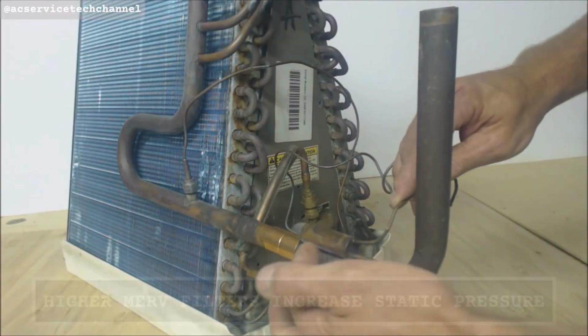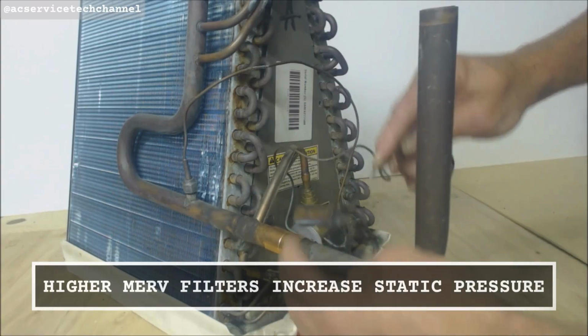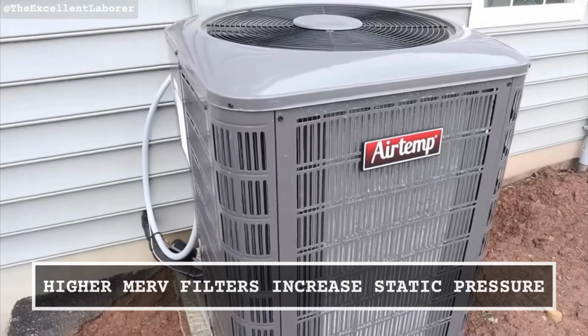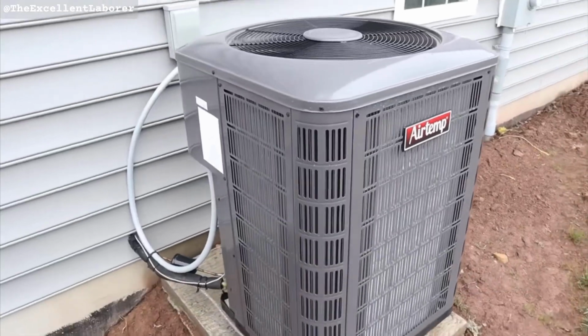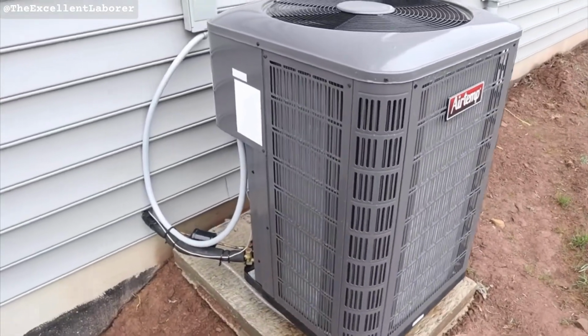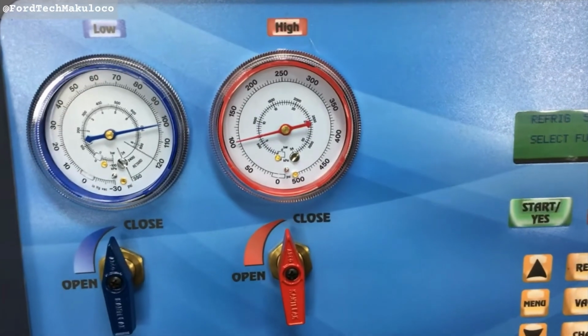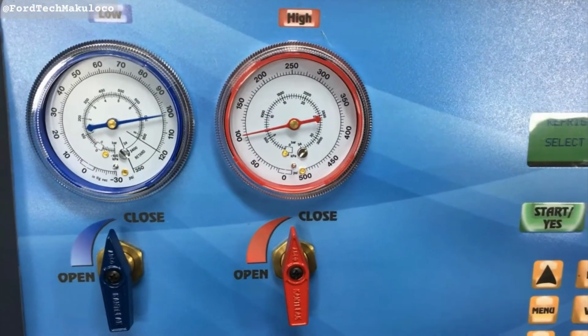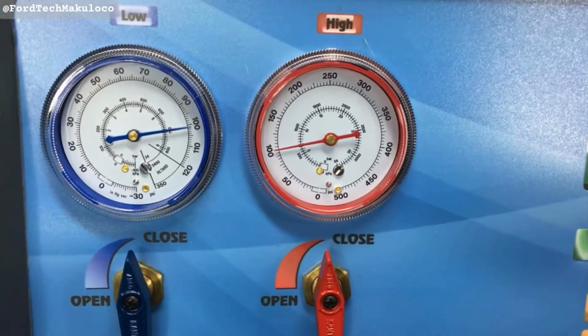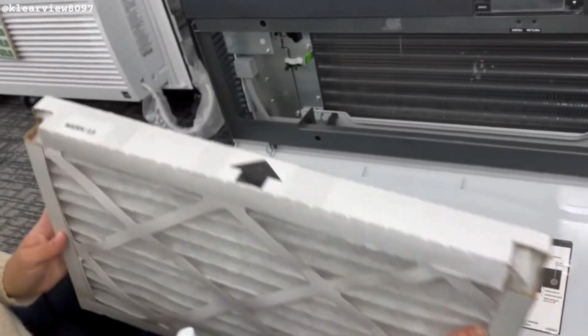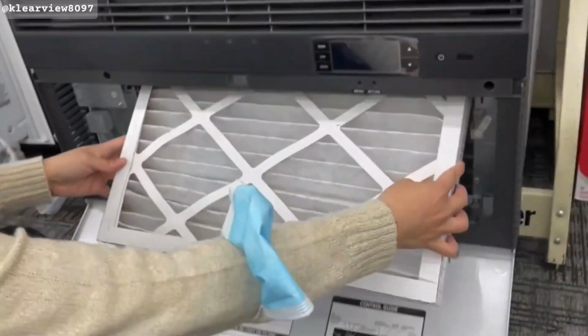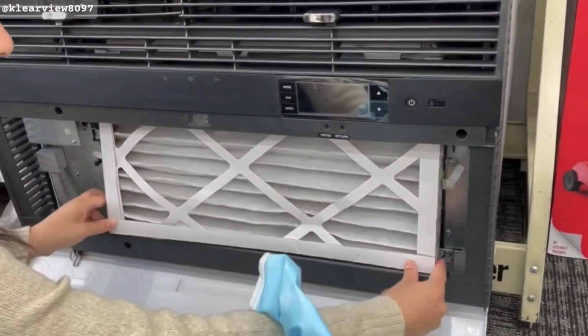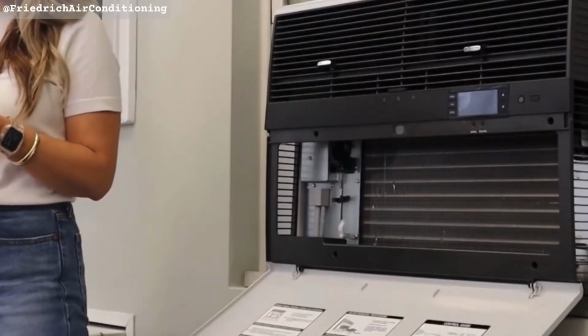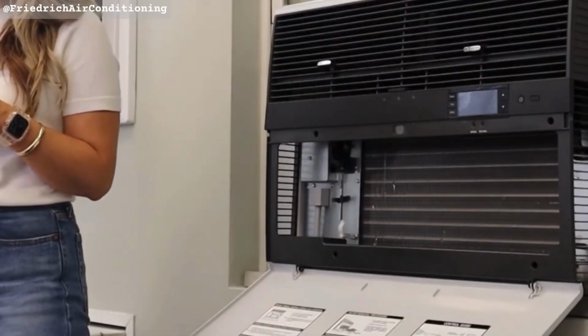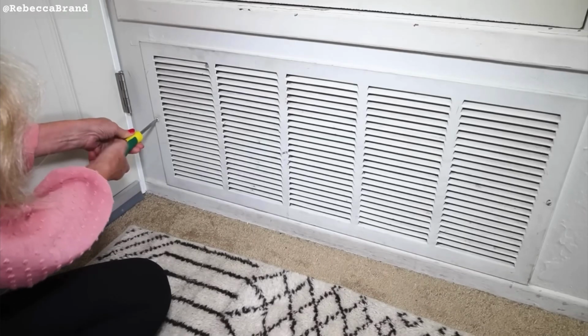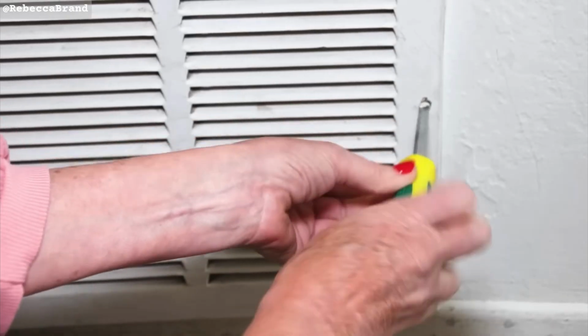Number 7. Each MERV rating above 8 adds roughly 0.05 of an inch of water column to your system's static pressure. A typical residential system is designed for a total external static pressure of 0.5 inches of water column, about the pressure it takes to lift a sheet of paper into a fan. Install a MERV13 filter on a system already running near max static and you've pushed it into the red zone. Blower motor draws more amps, runs hotter, fails earlier. The filter aisle does not advertise this part.